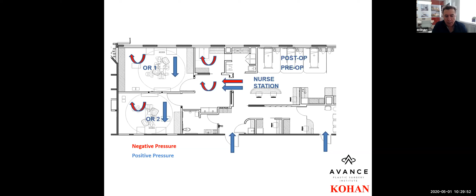So when I talk about the doors, if you wanted to add a door to your open operatory or your open exam room, then maybe the swing door is the best because it's pretty tight. But if you do a pocket door, that's the next best. I would eliminate the barn door, I think it would be too much leakage. And if you have no door, then you really can't do a negative pressure.